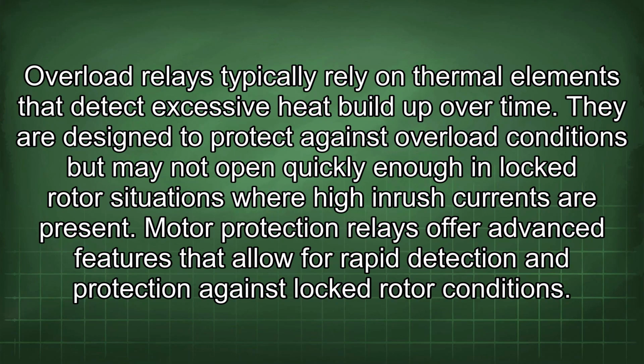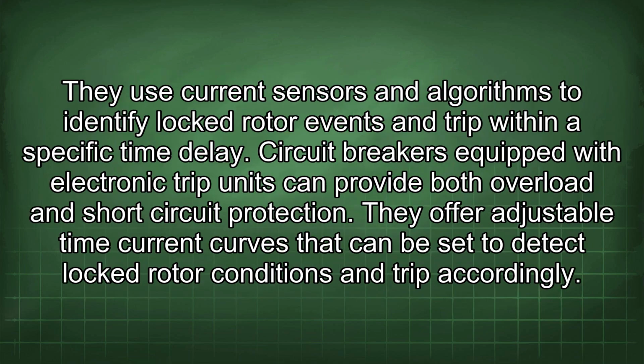Overload relays typically rely on thermal elements that detect excessive heat buildup over time. They are designed to protect against overload conditions, but may not open quickly enough in locked rotor situations where high inrush currents are present. Motor protection relays offer advanced features that allow for rapid detection and protection against locked rotor conditions. They use current sensors and algorithms to identify locked rotor events and trip within a specific time delay.